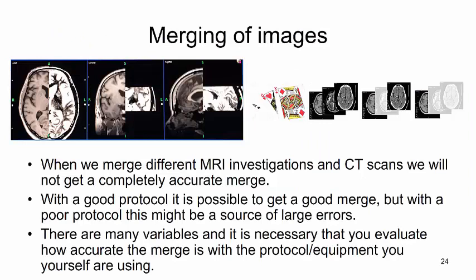Regarding merging of images. When we merge different MRI investigations and CT scans, we will not get a completely accurate merge. With a good protocol, it is possible to get a good merge, but with a poor protocol, this might be a source of large errors. There are many variables and it is necessary that you evaluate how accurate the merge is with the protocol and equipment you yourself are using.